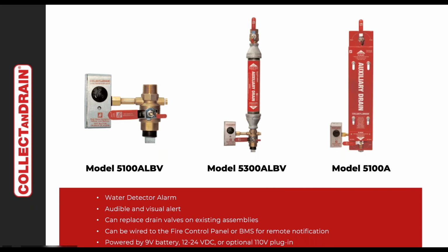Now, it also has dry contact, so it can be wired back to a fire alarm panel to send a trouble signal. It can also be integrated into a building management system so that it would indicate on the building management system which low point drains needed to be emptied. And it has the unique feature, again, taking industry comments, it can be powered from a simple 9-volt battery, or it can use the low voltage alarm loop wiring, or it can even be plugged into a local lighting connection.